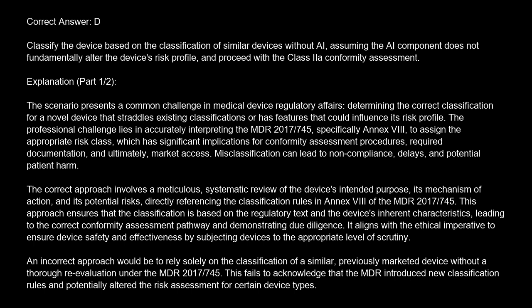The correct approach involves a meticulous, systematic review of the device's intended purpose, its mechanism of action, and its potential risks, directly referencing the classification rules in Annex VIII of the MDR 2017/745. This approach ensures that the classification is based on the regulatory text and the device's inherent characteristics, leading to the correct conformity assessment pathway and demonstrating due diligence. It aligns with the ethical imperative to ensure device safety and effectiveness by subjecting devices to the appropriate level of scrutiny.